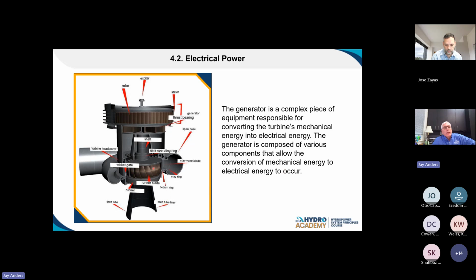Yeah, it's more what you're saying there at the end. It just gets us to that instantaneous reaction. It allows us to very rapidly control what's going on with the unit. Typically, for a lot of our traditional pump storage plants, we have to completely turn them off. If they're pumping, we have to go clear back down to zero before bringing them back online. With a ternary unit, you're hydraulically taking it through those zero points just by making the water go out in the pump direction up the hill, or letting it go on out to your lower reservoir into gen mode. A lot of it has to do with hydraulics, there's nothing electric per se, except you're using electricity to run the unit.